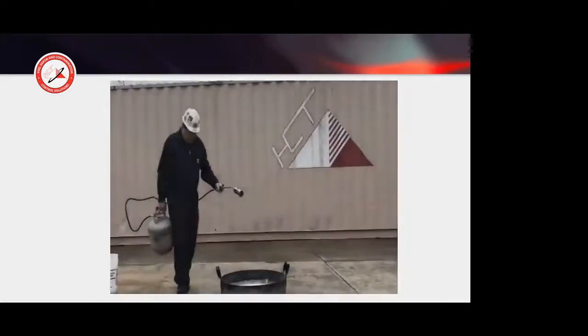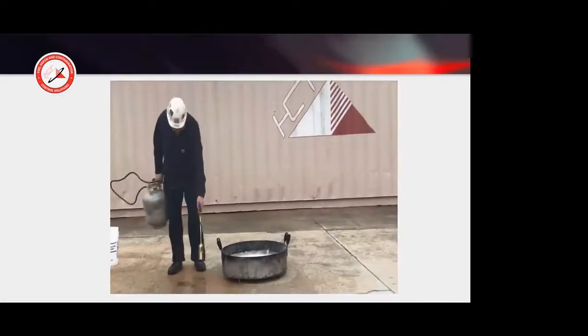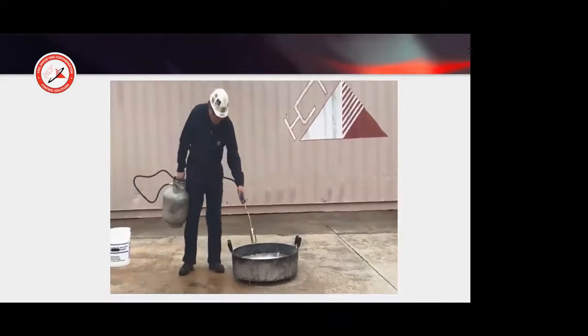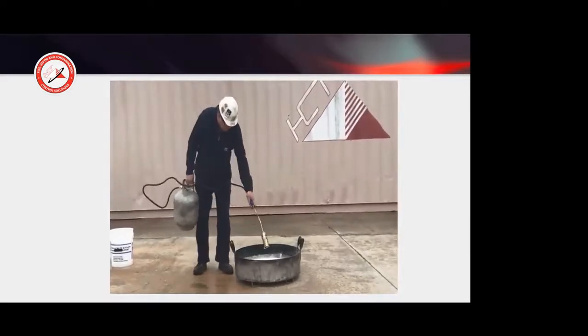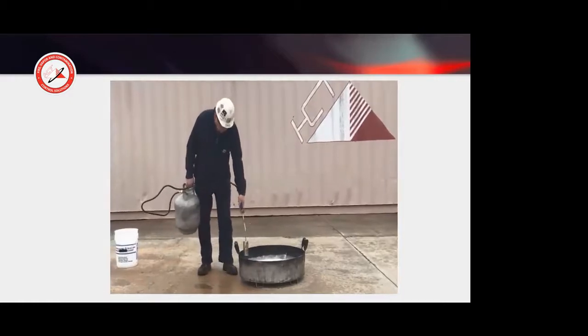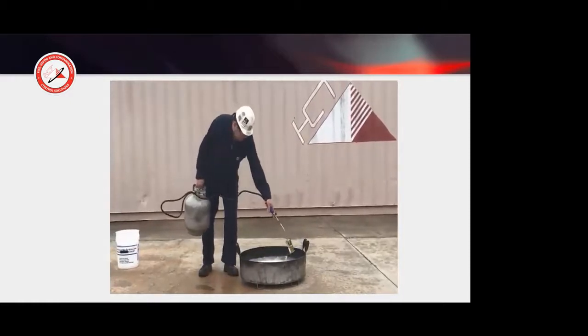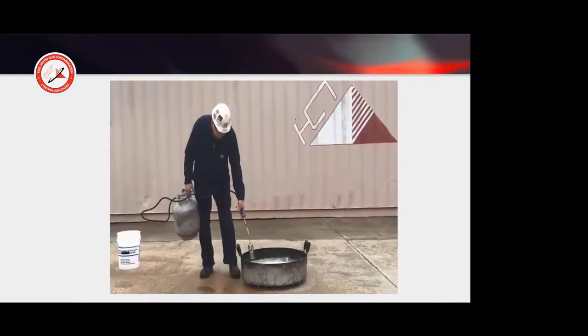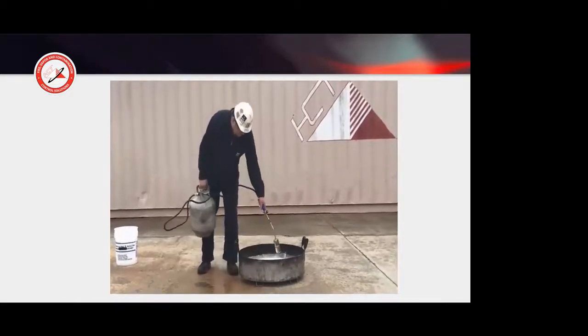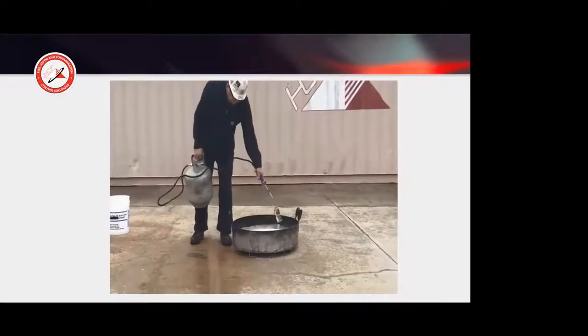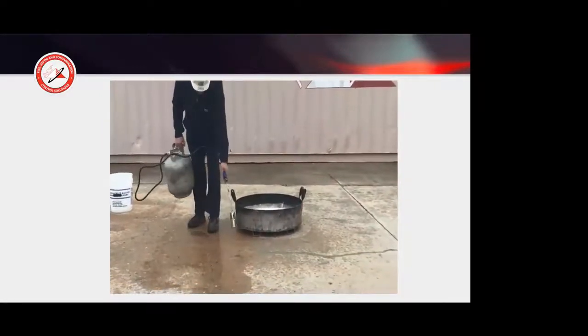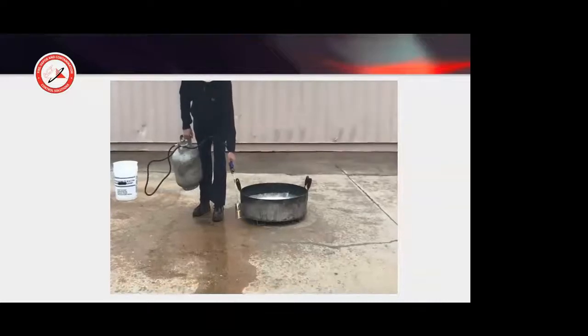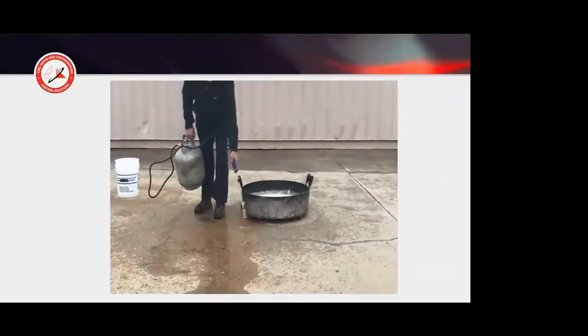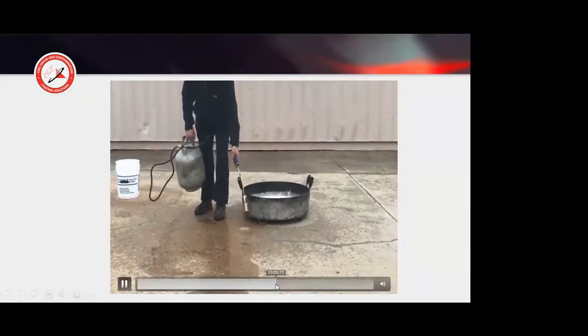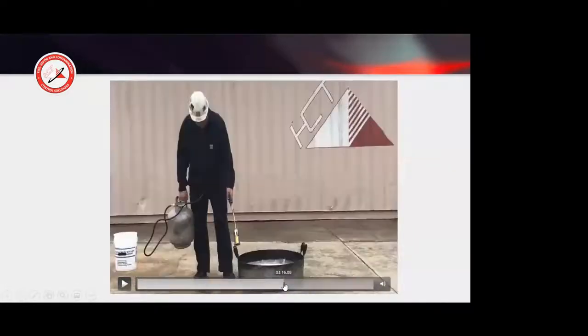And then after you've encapsulated, you wait 1 minute, and then you have to apply a flammable torch to the entire surface of this pan. So if this agent is a wetting agent and does not form any foam blanket, then this pan will instantaneously ignite because we haven't blanketed the fuel and we haven't encapsulated the fuel. So hence the 1 minute test.